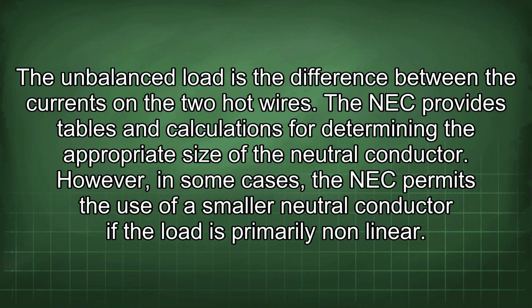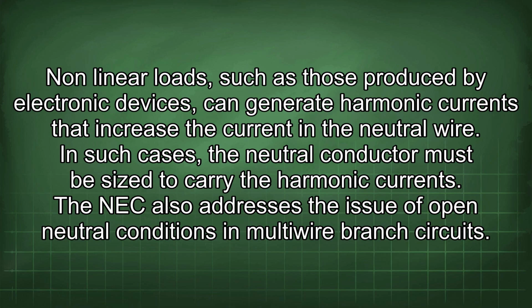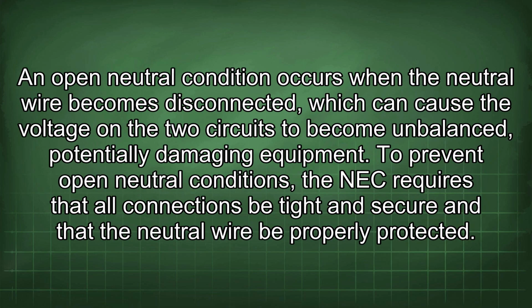However, in some cases, the NEC permits the use of a smaller neutral conductor if the load is primarily nonlinear. Nonlinear loads, such as those produced by electronic devices, can generate harmonic currents that increase the current in the neutral wire. In such cases, the neutral conductor must be sized to carry the harmonic currents. The NEC also addresses the issue of open neutral conditions in multi-wire branch circuits. An open neutral condition occurs when the neutral wire becomes disconnected, which can cause the voltage on the two circuits to become unbalanced, potentially damaging equipment.